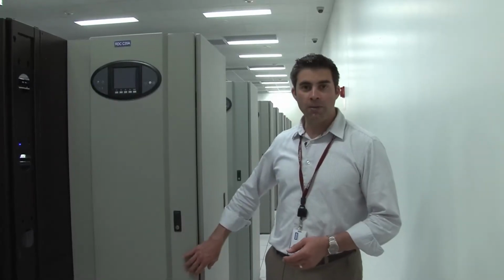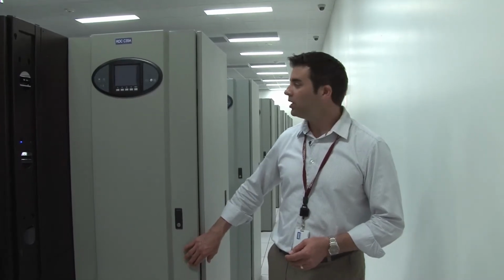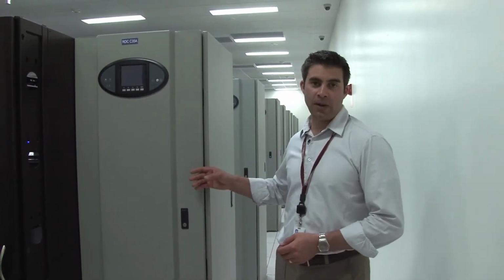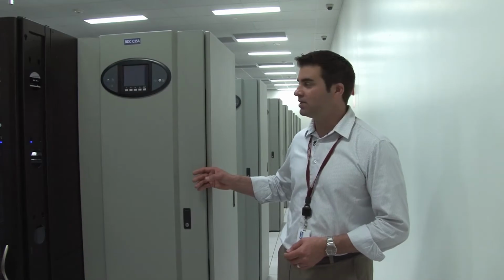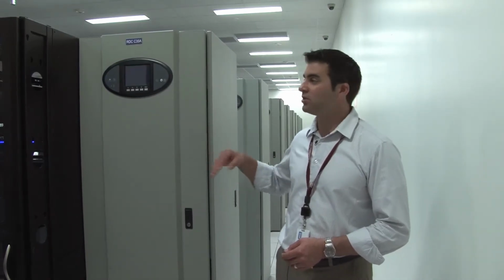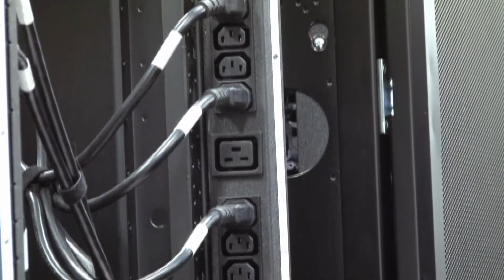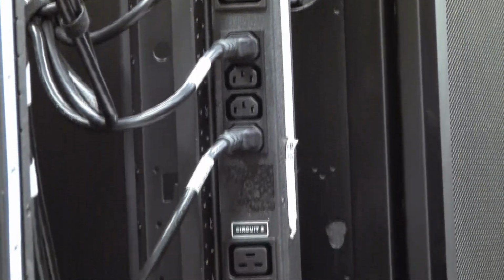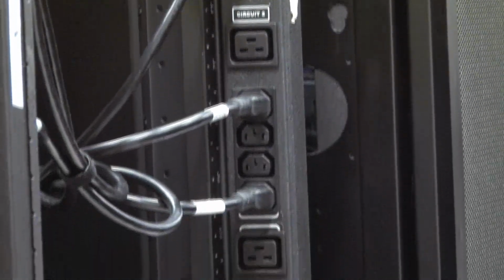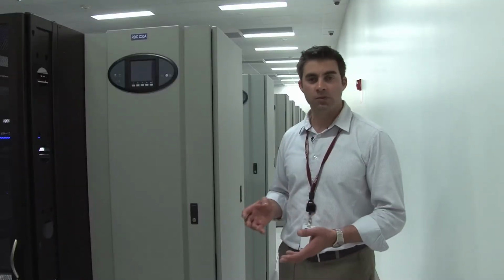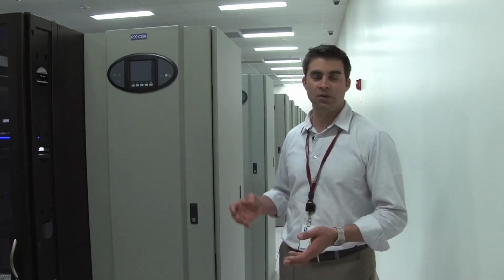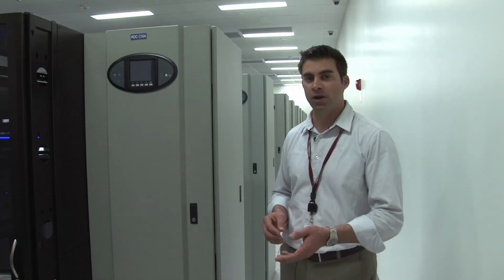This is a remote power panel on our data center raised floor. This provides the A power source to all of our redundant feeds. And the B power source is on the other side of the aisle. So what we do is we provide a circuit out of the A side and a circuit out of the B side, and customers are allowed to plug into both with their dual cord equipment, knowing that if one side was to fail, the other side would always be available for them.